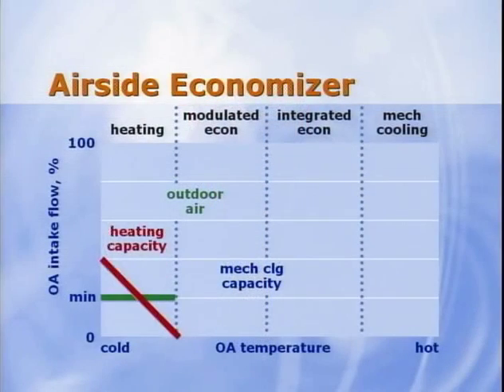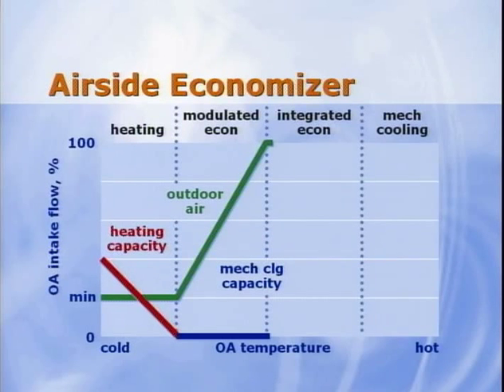First up is John with Economizer controls. An Airside Economizer is a common energy-saving control strategy that uses outdoor air as a source of free cooling whenever possible. When the dry bulb temperature of the outdoor air is colder than the supply air, the controller modulates the positions of the outdoor and return air dampers so that the mixture provides supply air at the desired temperature. In this modulated economizer mode, the outdoor air is cool enough to handle the entire load, so the compressors are shut off. This saves cooling energy.